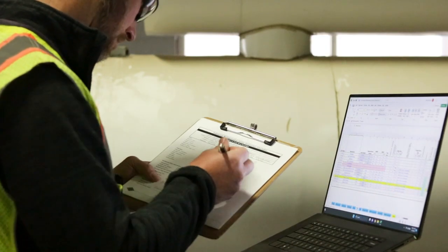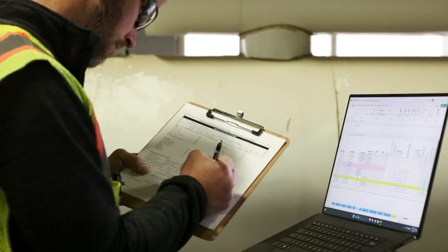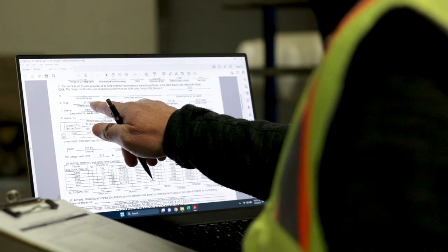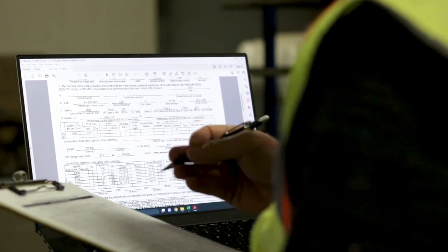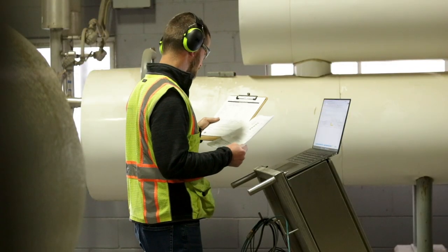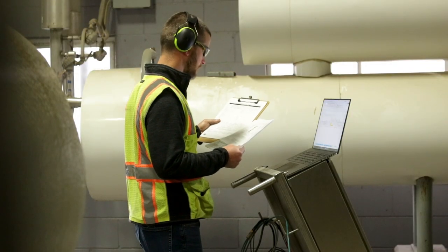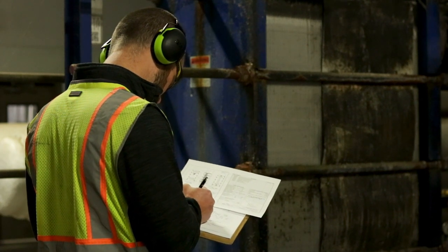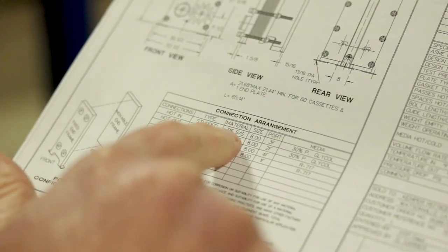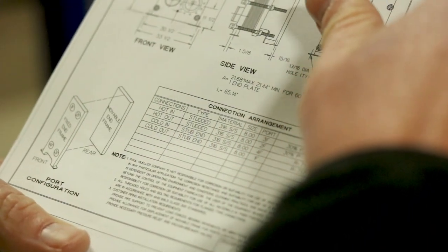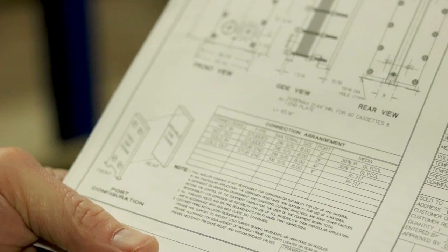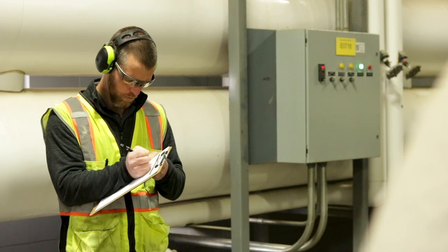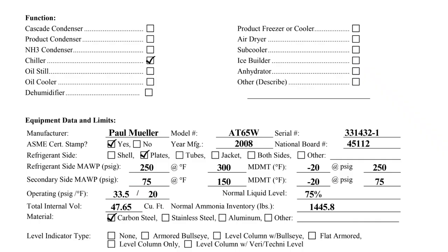The internal volume for a plate and frame heat exchanger should be provided by the manufacturer. Using the volume, the normal ammonia inventory is typically calculated using a spreadsheet. For a shell and tube heat exchanger where ammonia is in the shell, the internal volume can be calculated by subtracting the total tube volume from the volume of the shell. If unknown, the heat exchanger's material can be determined from the manufacturer data report or U1 form and manufacturer specification sheet. The plates on this heat exchanger are constructed of stainless steel, while this shell and tube heat exchanger is constructed of carbon steel.